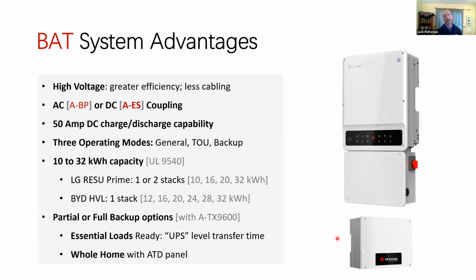So on the battery side, now we're getting away from just being a PV inverter, but for our battery only or our energy storage inverter, the hybrid inverter, you have these features. High voltage, that's the number one thing that is usually new to someone. We do high voltage connections to batteries because high voltage is more efficient. When you run high voltage wires at high voltage, you have less loss, so less voltage drop. Also, it means you're using thinner cables, so that's less copper, less costly.